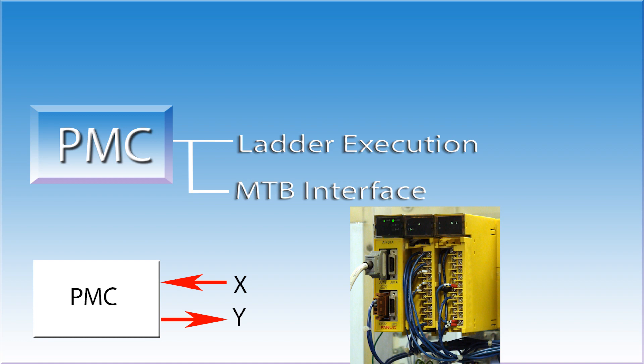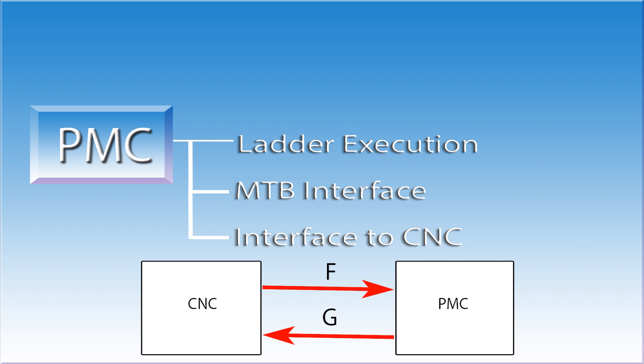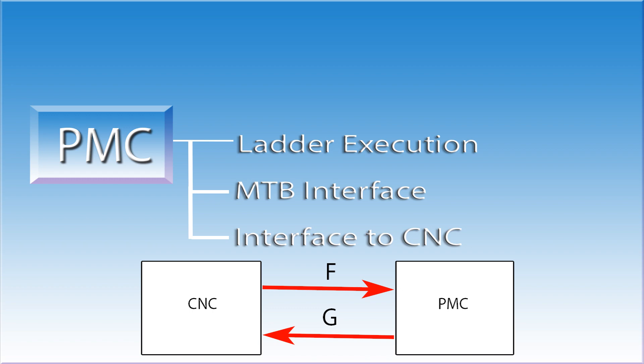The third area of responsibility for the PMC is the CNC interface. Remember, the CNC and the PMC are always talking to each other. This is how the CNC finds out what is going on in the real world, and the PMC sees what the CNC wants to see happen. The last area of responsibility for the PMC are the machine tool builder alarms. These alarms will typically start with a 1000 or 2000 number.